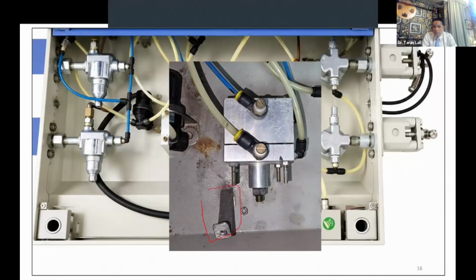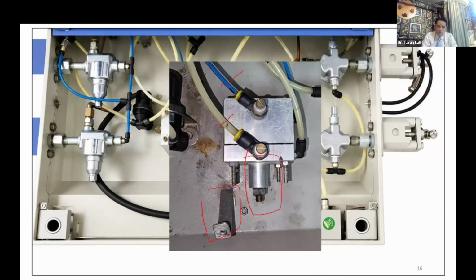So you see that it has connections from both oxygen, the white one, and nitrous oxide. So what could this be? This probably indicates that it is some kind of a pressure sensing device. So this is probably a master slave device where the nitrous flow is controlled by the flow or the pressure of the oxygen pipeline. If the oxygen line is exerting enough pressure, only then it will allow the flow of nitrous oxide. So this is a master slave assembly, again a hypoxia prevention device.